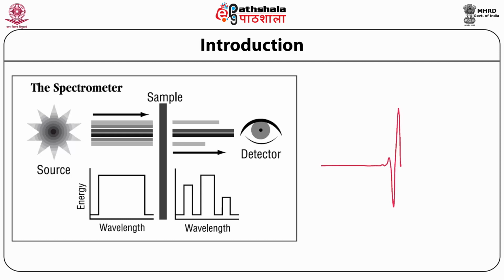Point 3, the sample. The beam enters the sample component where it is transmitted through or reflected off the surface of the sample, depending on the type of analysis being accomplished. This is where specific frequencies of energy which are uniquely characteristic of the sample are absorbed. Point 4, the detector. The beam finally passes to the detector for final measurement. The detectors used are specially designed to measure the special interferogram signal.